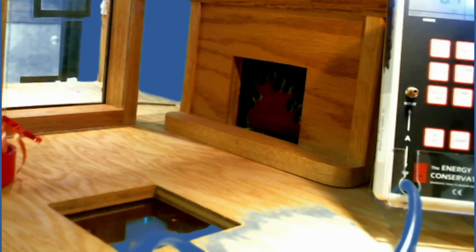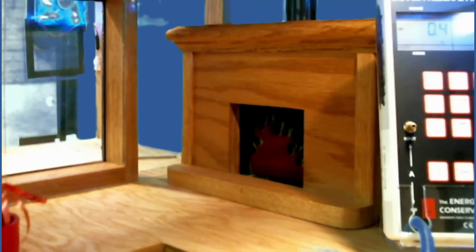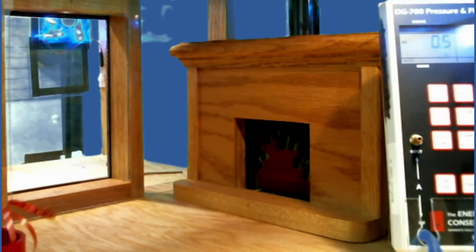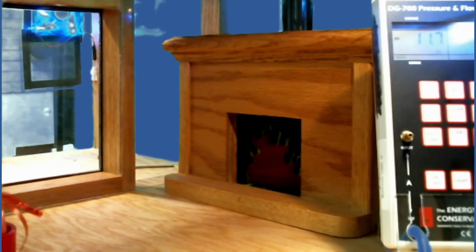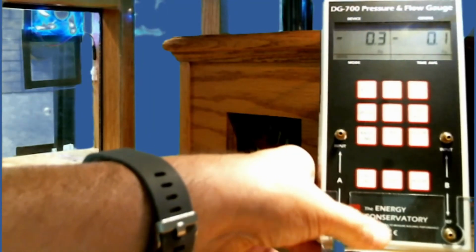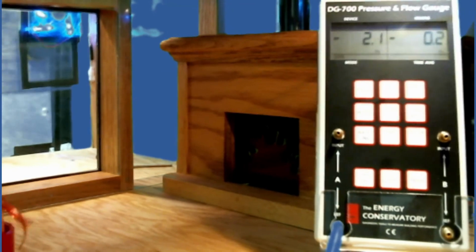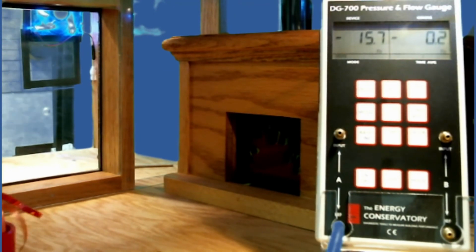Now, if I want to see the manometer reading there again, we can kind of see the numbers there. I'm going to put my window back on the front door. Just right there a little bit better, you can see it. It's the number on the left. So that's if all 3 of those doors are closed. We're at about -15.